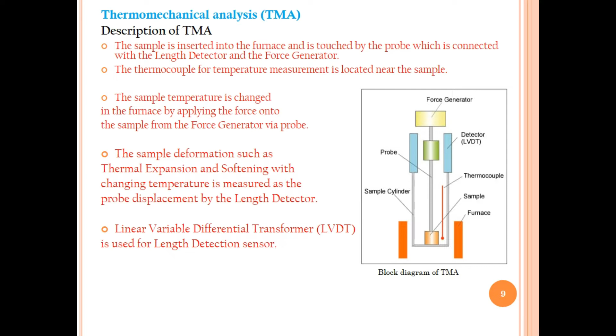The thermocouple for temperature measurement is located near the sample because it is used to measure the temperature changes during the TMA operation. The sample temperature is changed in the furnace while force is applied on the sample from the force generator via the probe. The sample deformation, such as thermal expansion and softening with the changing temperature, is measured as the probe displacement by the length detector. The probe displacement measures how much the sample is softened or hardened after applying the force along with the temperature. The linear variable differential transformer, LVDT, is used as the length detection sensor. LVDT is used in all the dynamic techniques, meaning DMA and TMA, as the sensor for length detection, while the thermocouple in DMA and TMA is used for the change in temperature of the sample as well as the reference in both types of techniques.